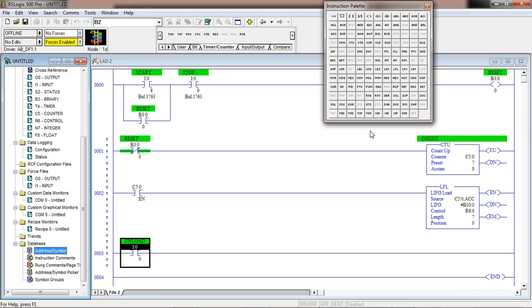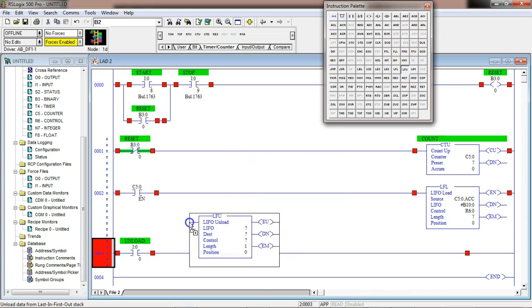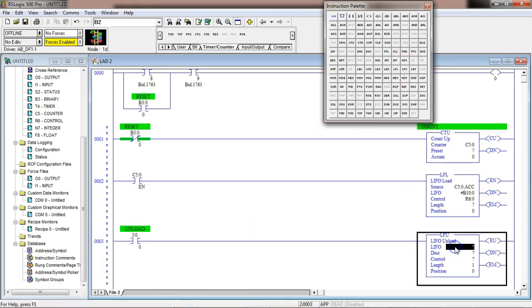We entered it directly in our Symbols table. Every time I hit the switch, we're going to come up and use Last In First Out Unload. Our LIFO stack is in B10. The destination is Output O:0.0. So this is our output. Our control register is R6:1, and our length will be 7.